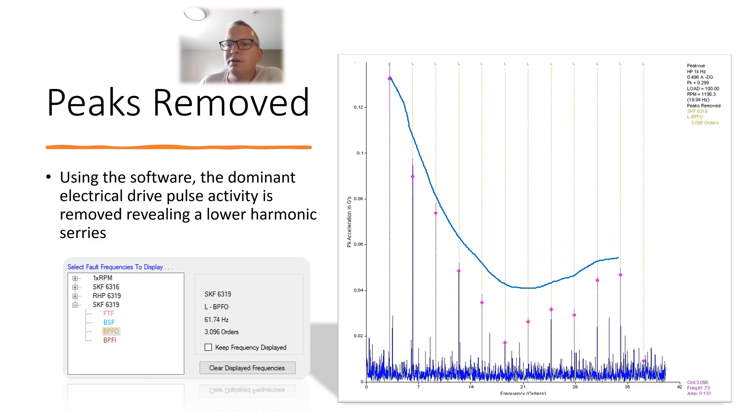So using the software, we've got the correct speed set up, put the bearings in and we confirm that this here is an inner race signal. So we're not seeing the velocity, we weren't seeing acceleration, this is purely in PeakVue. So we could say to them, this is a very early defect.